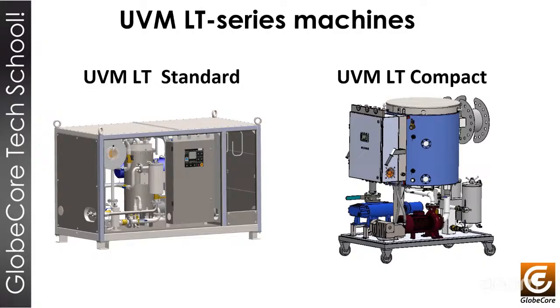Turbine oils and different industrial oils can be worked with this kind of machine. This equipment is designed to process oil with a higher level of particle contamination, owing to the use of enlarged mechanical filters at the inlet of the machine. The filtration thickness on the new filters is 100 to 200 micron. This is the inlet filter. Then you will see in the next slides we have other filters, and this filter can remove the solid particles in the process in a better way.